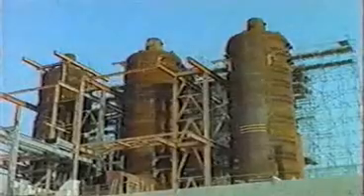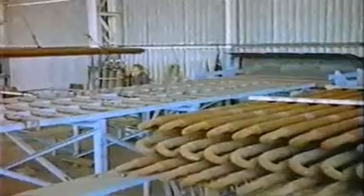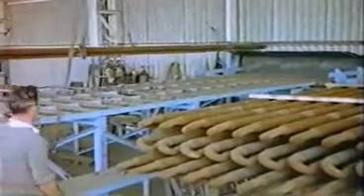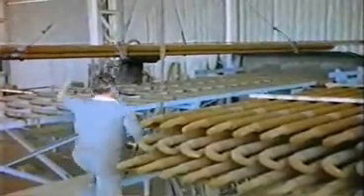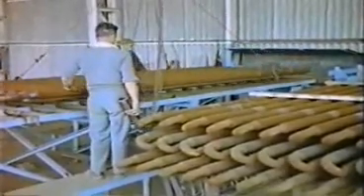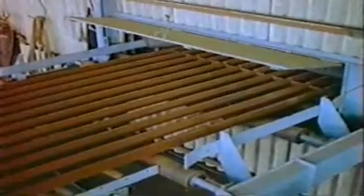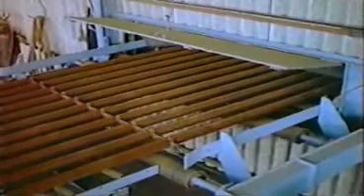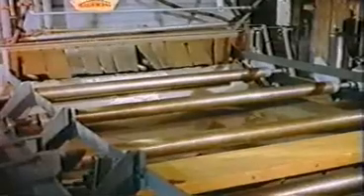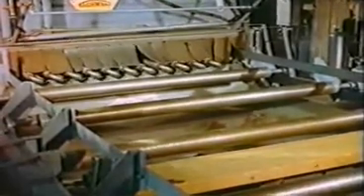By the time we had erected 3 boilers, all on the north side of number 1 reactor, clean conditions had been achieved within the first one, and tubing up operations were in progress. All the tubing, except the superheater banks, is of the integral finned type. Before dispatch to site, the tubes are tested ultrasonically to ensure that none of the welds will fail in service. On site, they are cleaned externally by a shot blasting process prior to being inserted in the boilers.